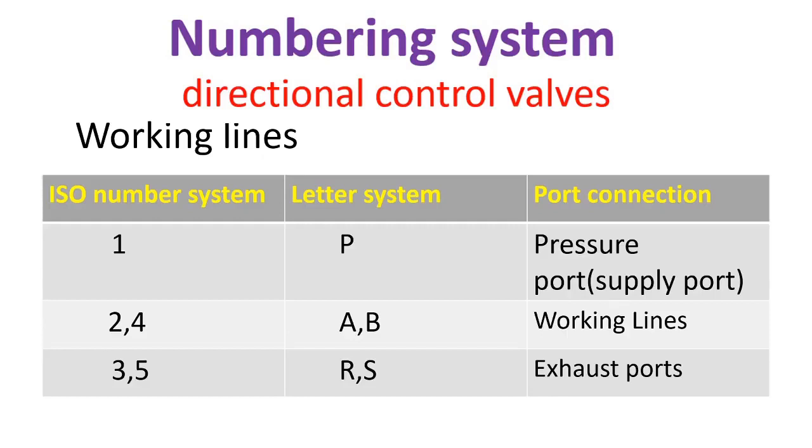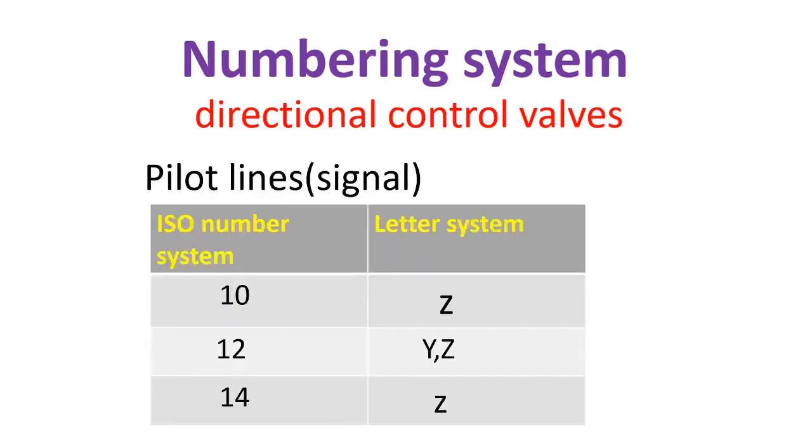For number 1 and letter P, that is pressure port or supply port. For number 2 and 4 or A and B, that is working lines. For number 3 and 5 or R and S, that is exhaust ports. And for our pilot lines or signal, 10 is equivalent to Z, 12 is equivalent to Y or Z, 14 is equivalent to Z.